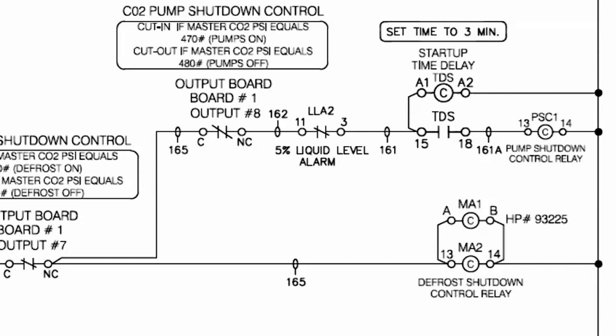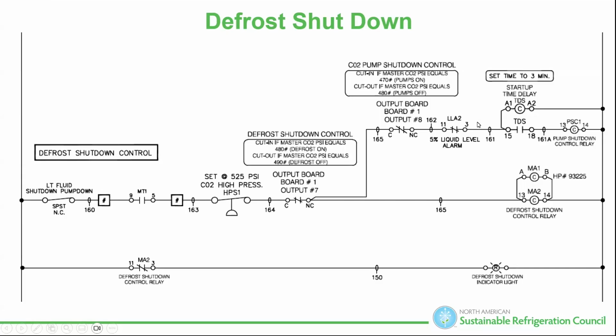So if I walk into this motor room, or somebody calls me and says, hey, I'm on this overfeed system, I can't get either pump to run - neither pump is running, well, you just told me part of the problem. PSC1's not energized. Well, look at all of these safeties that are in that circuit - any one of these safeties can turn this off.